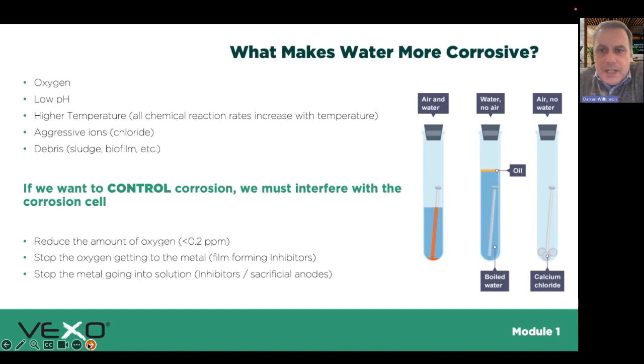We want to keep oxygen out of a closed loop system, which is why, depending on system parameters, you'll see a dirt and air separator, a vacuum degasser, or possibly a sacrificial anode as used in the VDI standard. There are various ways to manage oxygen, but the point is that once the system is filled, we want to get all the oxygen out as best we can.